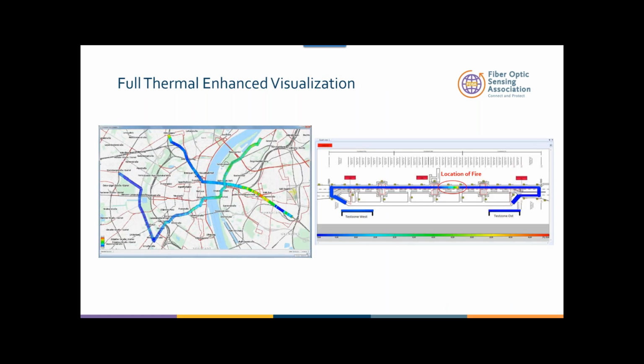The third thing is software that can tell you exactly where the thermal events are, because we are measuring temperature every single meter. We can tell you in a map or in your assets. On the left is a map of a subway system in Germany, where you can see the temperature monitoring. On the right, you can see when it gets too hot or too cold. It also gives operators the ability to understand whether this tunnel is being ventilated properly or not. On the right-hand side is another example with an enhanced visualization, where it gets very cold or very hot and you can see the location of a fire. This gives operators the ability to pinpoint exactly where the problem is and intervene at the right location at the right time.